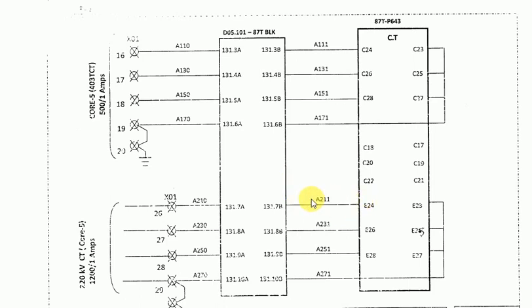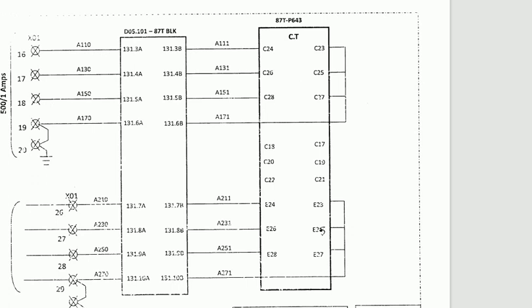Here you can see the scheme drawing for differential protection of a transformer. Since it is a unit protection, a minimum of two CTs is required to calculate the differential current. I am using two CTs here — one is the HV side CT and one is the LV side CT. In the differential relay system configuration, we have to configure this CT arrangement in the relay.